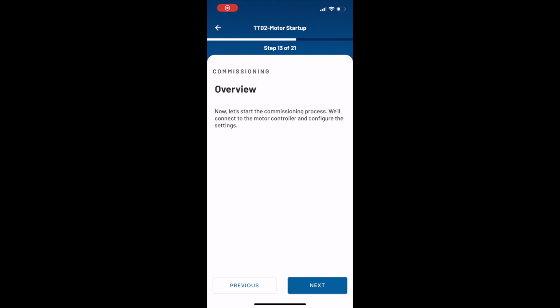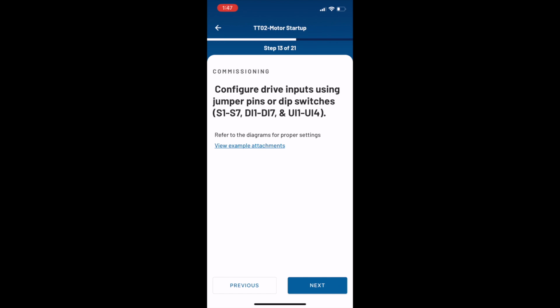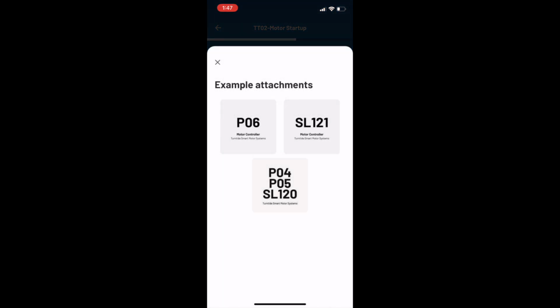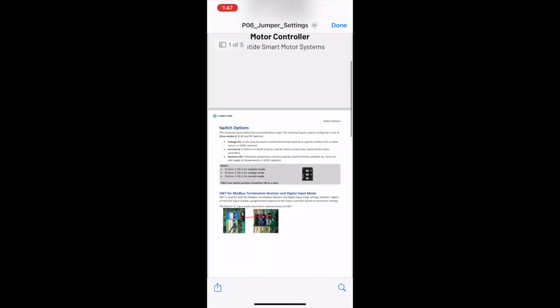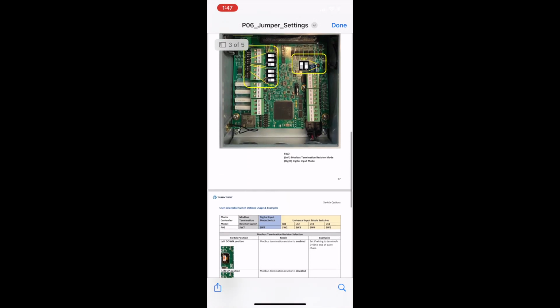It is now time to commission your motor system. You will first be prompted to configure the jumper pins or dip switches of your drive. Once you have completed this work, please tap Next. Note that you can find information about jumper pins and dip switches by tapping the View Example Attachments link and selecting the manual for your drive.